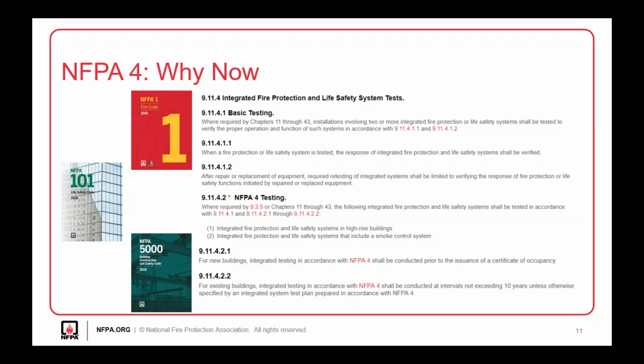So in these codes, some form of integrated system testing is required for all fire protection and life safety systems. What the code says is that when a fire protection or life safety system is tested, the response of integrated fire protection and life safety systems shall be verified. So for example, if you're performing fire alarm testing, you need to verify that all the integrated systems are responding as intended. If you notice, that section doesn't actually note NFPA 4, and the reason is that you're not required to follow the requirements of NFPA 4. However, it can serve as a good guideline when you're doing that confirmation.